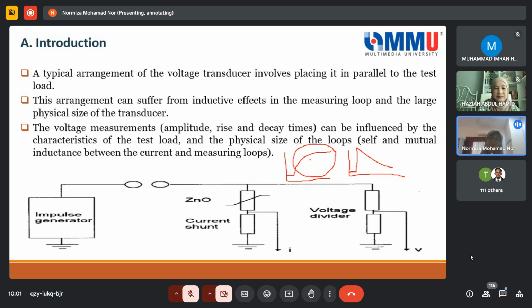Of course we do not want this response, because when we have this response, it means that your equipment is not characterized according to the spec, because the spec says you have to produce the fast response. This is coming as a fast response from the generating circuit, and then also applied here still as a fast response, but because of your measuring device and the inductive component that you have, I mean the inductance in the equivalent circuit representation, it will give the output as a delay here. Whereas in the manufacturer's data sheet, what you have to present is this one here, which should give 1.2/50. I think you have learned this one before, right? 50 microseconds for the impulse.